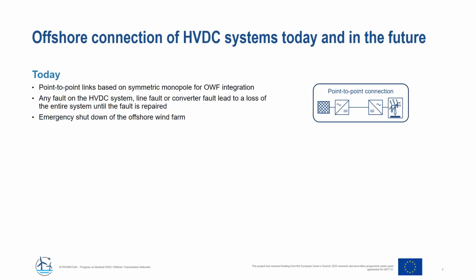Existing offshore wind farms are based on point-to-point links based on the symmetric monopolar configuration. So any fault on the HVDC system, be it a line fault or a converter fault, leads to a loss of the entire system until the fault is repaired, which might take several months in case of an offshore cable fault. So in case of any fault, there's an emergency shutdown of the entire offshore wind farm.